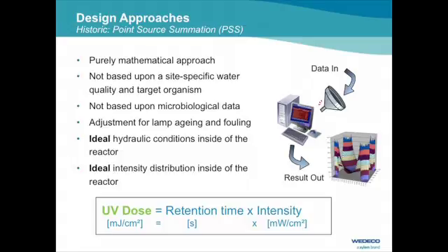especially for wastewater. That was a purely mathematical approach where you assumed basically the reactor's geometry and the lamp properties, and by that calculated the retention time and the intensity which is delivered by the installed UV lamps, and then you were coming to a UV dose. So that was a purely mathematical approach, assuming a number of ideal conditions and not considering actually the water's properties or the microbiology properties. And there are quite some differences.